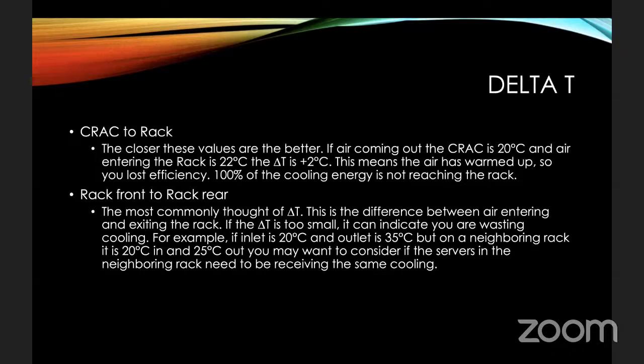This is why it's important to monitor the delta T at the front and the rear, because a lot of people put one temperature sensor in the cold aisle or one temperature sensor on the front of the rack. So this means they've got monitoring of the air temperature coming in, and they say, okay, my air temperature coming into my rack is 20 degrees. Everything's good. My cooling system's working great. A server overheats and they wonder why.